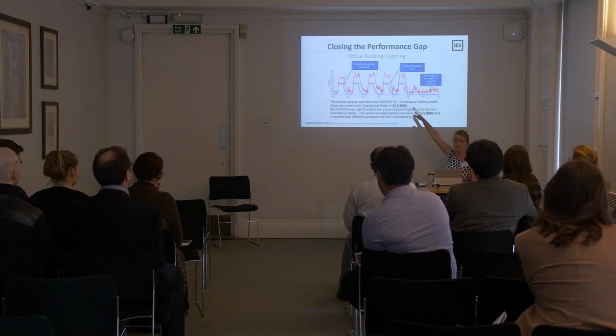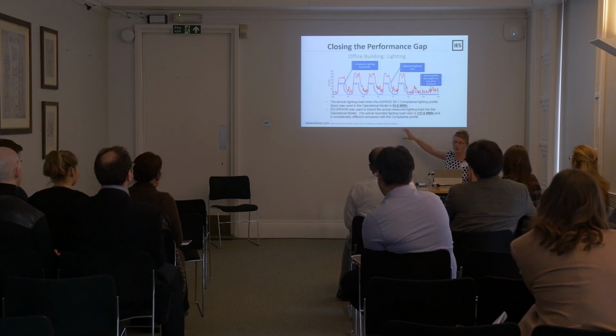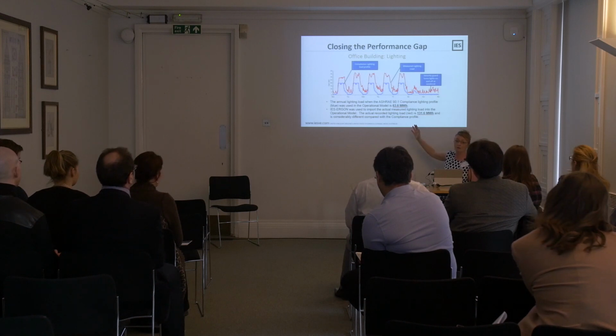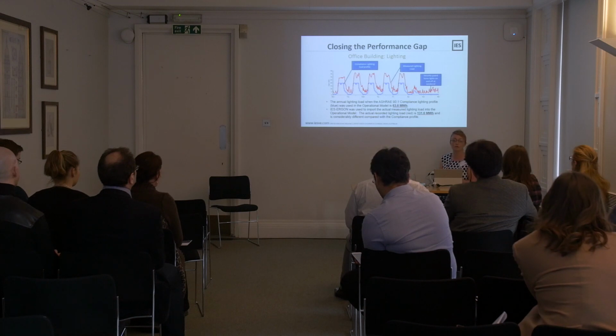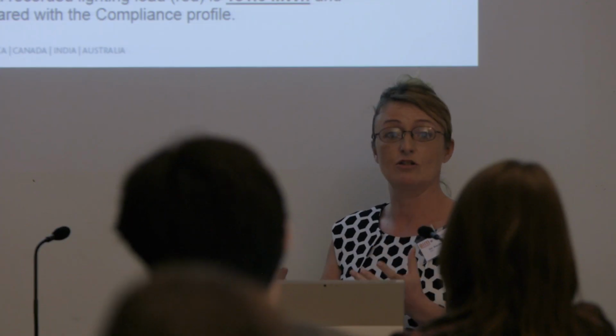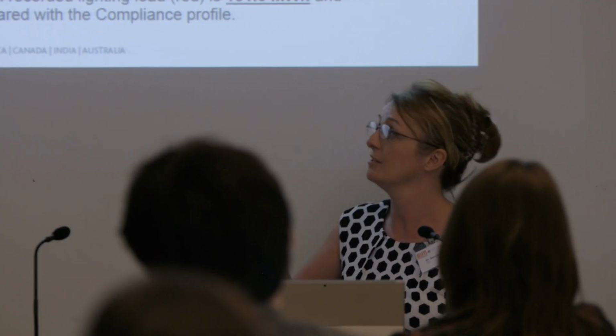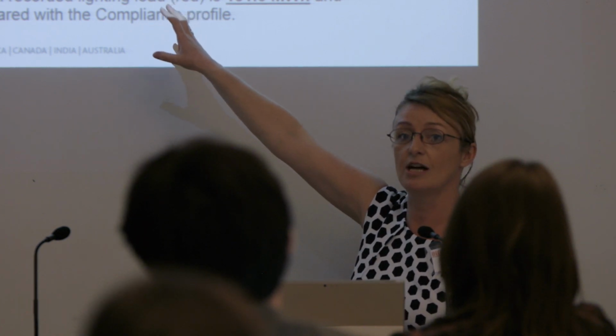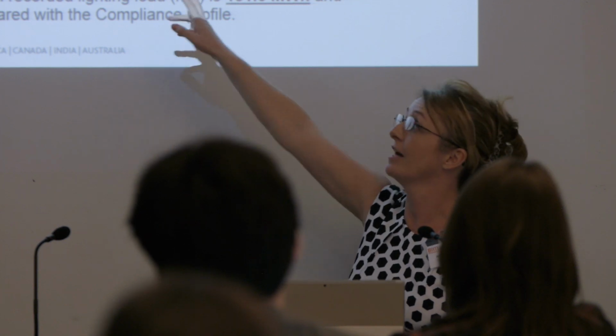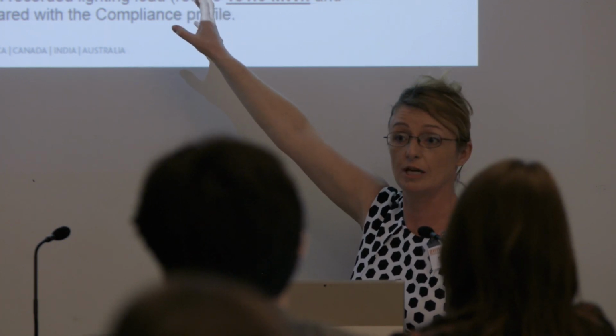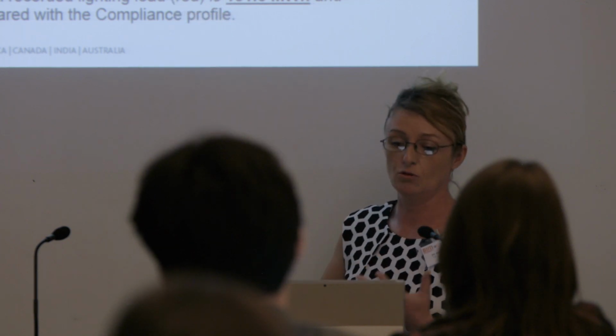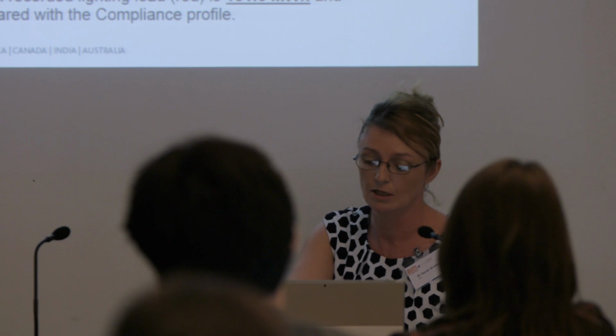It's dropping off at lunchtimes every day and then dropping down at weekends as you'd expect, but the loads are actually double. That's got quite a large impact on the annual lighting energy for the building - more than double. It also has knock-on effects on heating and cooling, because the heating plant probably doesn't run full tilt since the lighting is actually heating the building. So we can start to really drill into how buildings are being used, asking why we're getting these sorts of things - is it because in the design stage we assumed some lighting control which wasn't actually installed, or maybe it's just not working? We start asking questions and figuring out where the energy's going.